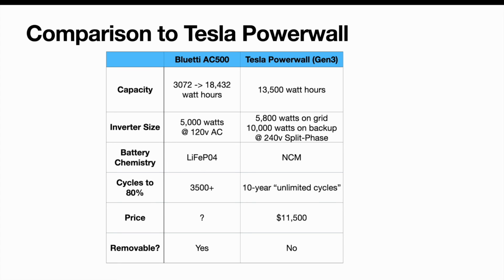The electrical code will not allow it. So even though you can get 10,000 watts out of the inverter of a single Tesla Powerwall, you have to size your transfer switch such that you are only getting 5,800 watts out of it.